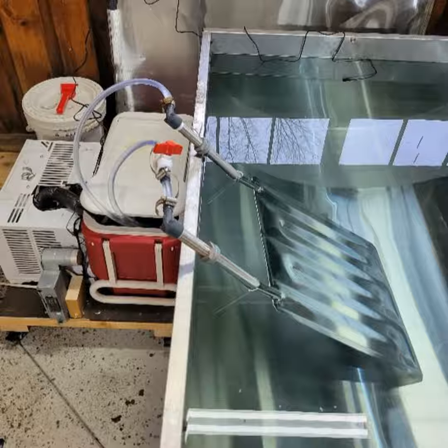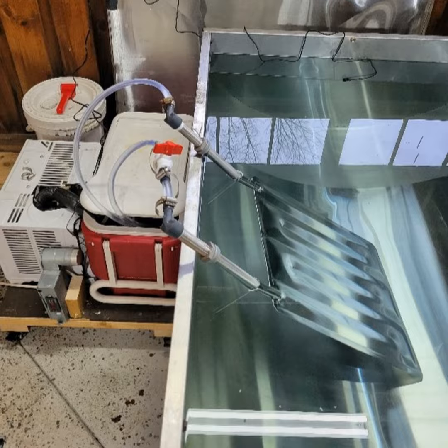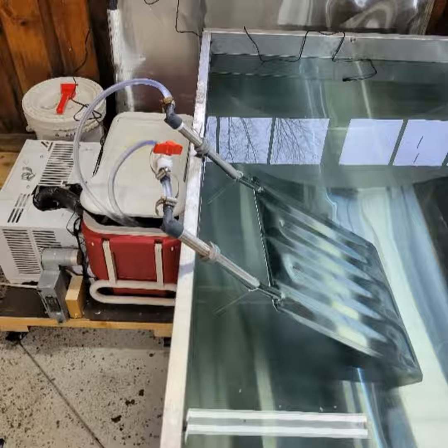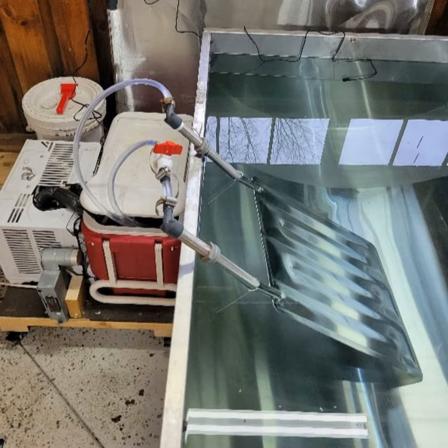It's all contained in one unit. You're not disconnecting lines and having to charge it with refrigerant and pressure tests and all that. It's all contained in one individual unit, and they usually have a tank on them. You put your glycol water solution into that tank, and then there are cooling coils within that little tank. There is a compressor with the refrigerant that pumps through the cooling coils that are in that tank that chills down the glycol water solution. So the refrigerant is all contained within that unit. And then they either have pumps or you add pumps or even a simple submersible pump right into that glycol tank, and you pump that chilled glycol out. You can connect it right to a milk tank and it'll feed through the cooling plates and then come back into that tank, where the cooling coil is, and chill that glycol back down.